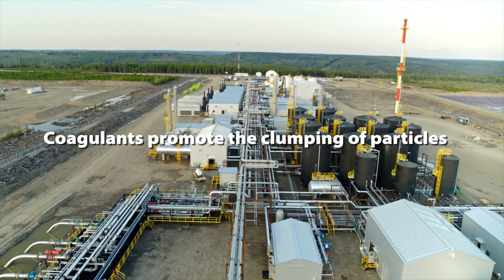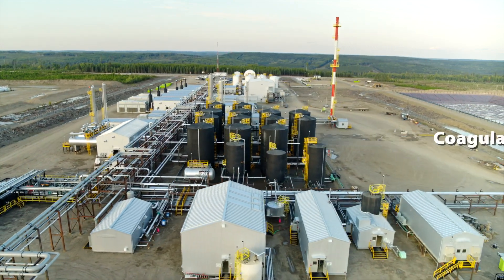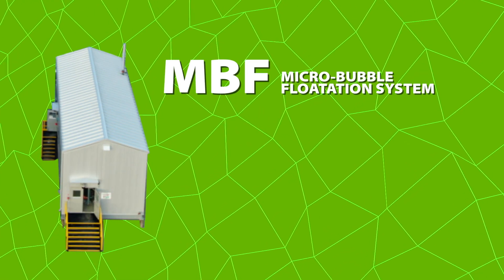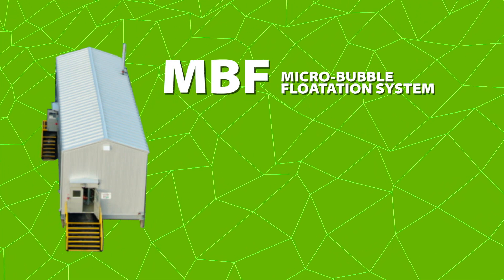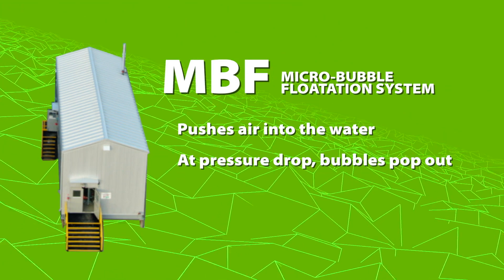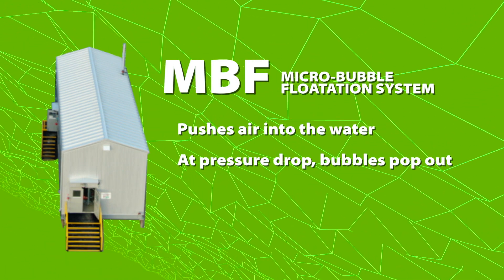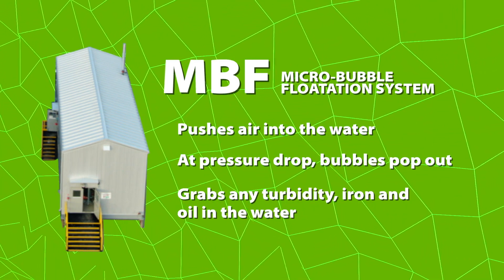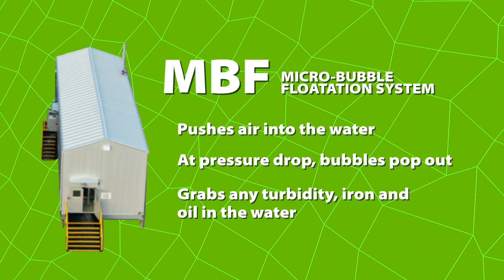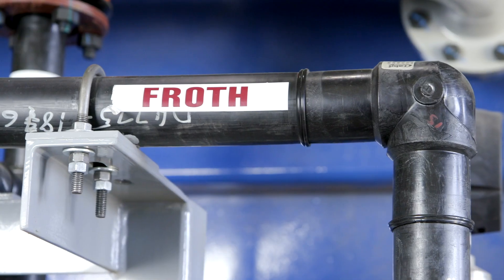The water then has coagulant injected into it, goes over to the MBF floc mixing tank where flocculant is mixed into it, then goes into the MBF, which is a micro bubble flotation system. It basically takes a whole lot of air, pushes it into the water, and then there's a pressure drop — at that pressure drop all of the bubbles pop out and it grabs any turbidity, some iron, and any tiny particle oil, bubbling them to the top and creating froth. All of the froth will float over to the froth box.